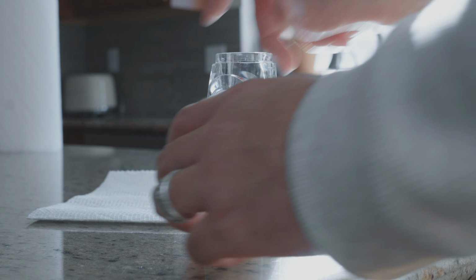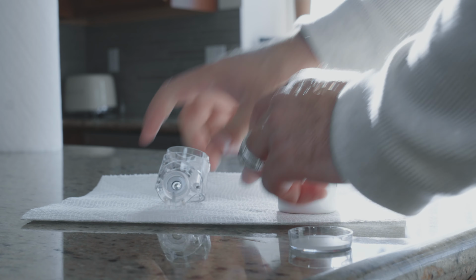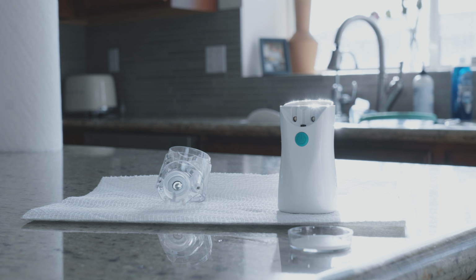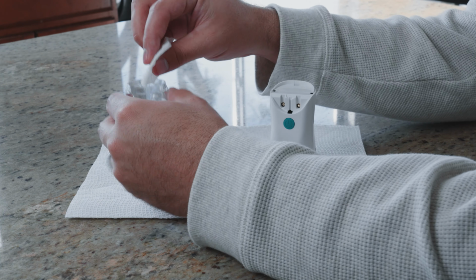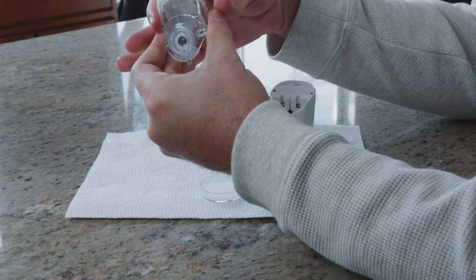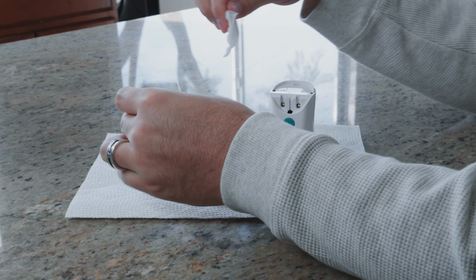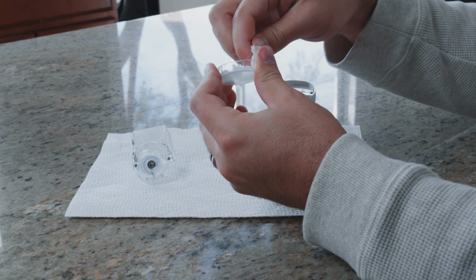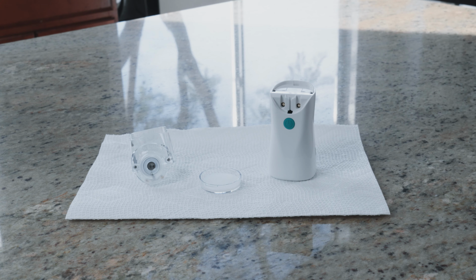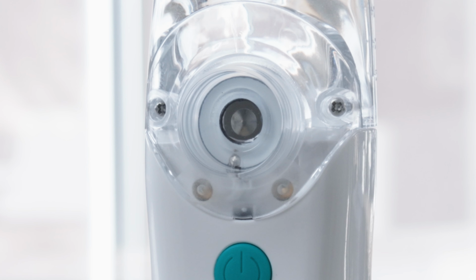Separate the main unit from the reservoir by firmly holding the main unit and gently pulling up on the reservoir. Do not wash or submerge the main unit, but it is okay to wipe down the unit with a soft cloth or medical-grade alcohol wipe. Wipe all of the components, including the cap, inside the reservoir, outside of the reservoir, electrodes, and the outside of the mouthpiece connector with a medical-grade alcohol wipe. Be careful not to touch the metal mesh plate on the outside of the reservoir. This may obstruct the atomizing plate and inhibit the flow of medicine during use.